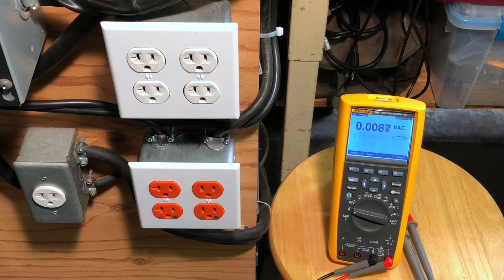The digital multimeter I was using, that Fluke 289, in the standard AC volts mode has a very high impedance, over 10 mega ohms. It doesn't really load the circuit enough to remove that ghost voltage. You might be asking, can you be shocked off of that ghost voltage we were measuring? Usually not. But in some cases, you might get a slight tingling sensation that might be noticed. It is something to be aware of and be cautious of, but you should not be receiving a severe electrical shock from a ghost voltage. You might have a slight tingling sensation.